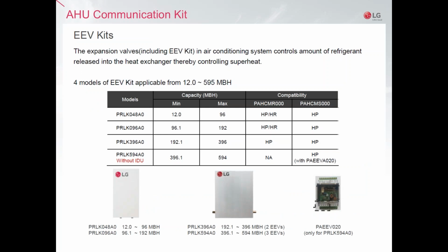The next step is to understand how to select the right EEV kit that we need. And for that, we need information on the actual load. I need to mention that all the EEV kits can work with either of the communication kits, with the exception of the largest size, the 594, which works only in supply air applications. The EEV kits include the electronic expansion valve, and these must be installed contiguous to the air handling unit, so they come in a NEMA box for outdoor installation. Some third-party handlers allow for the kits to be installed inside of them. The models are sizes 048, 096, 396, and 594.